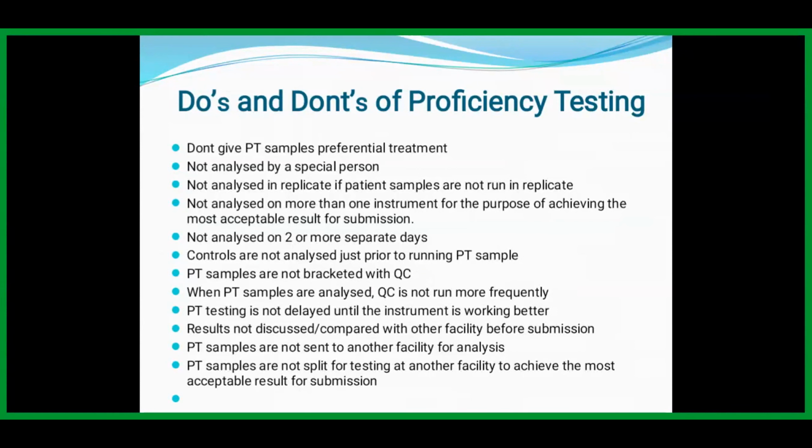When PT samples are analyzed, QC is not run more frequently. PT testing is not delayed until the instrument is working better. Results are not discussed or compared with other facilities before submission. PT samples are not sent to another facility for analysis.